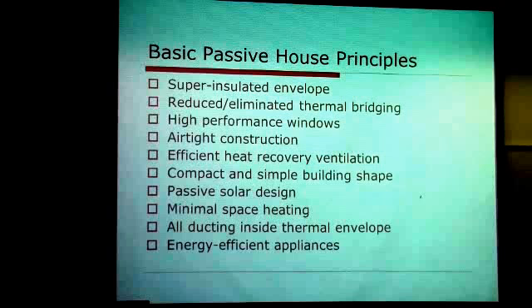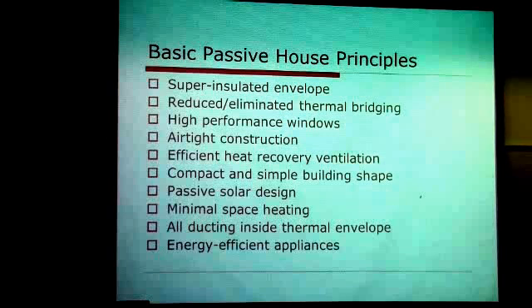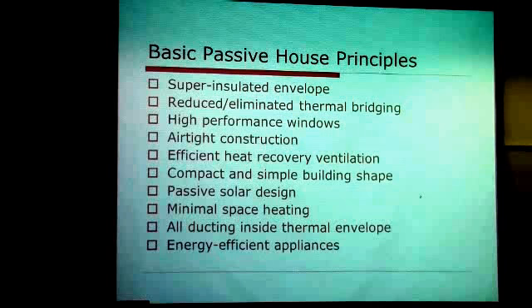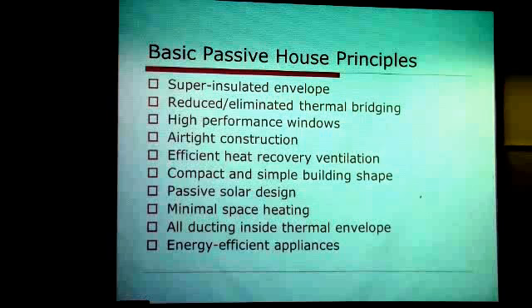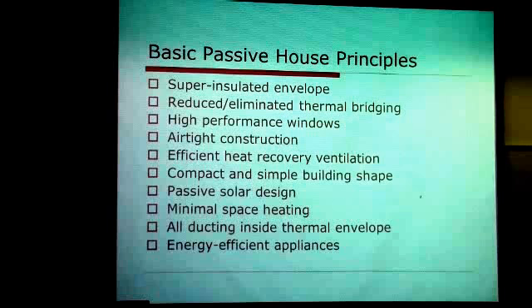Most times the HVAC contractor will oversize the system because he doesn't want callbacks. So the best way not to get callbacks is to oversize the system a little bit, but that also creates inefficiencies. So here you're really nailing down and saying, how much heat load do I have? What do I need the windows and walls to be to work together to meet these energy requirements?